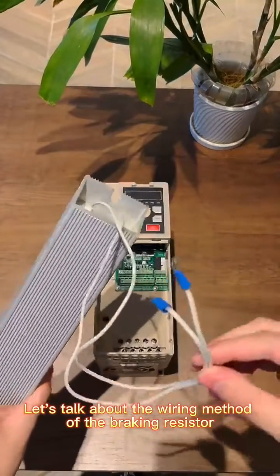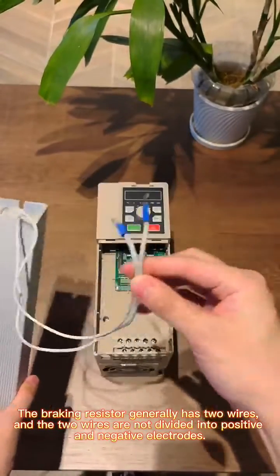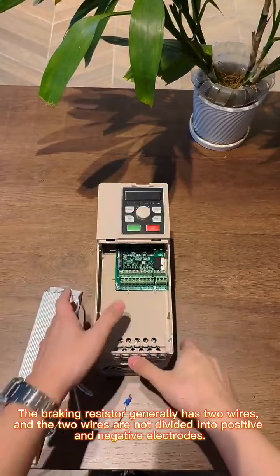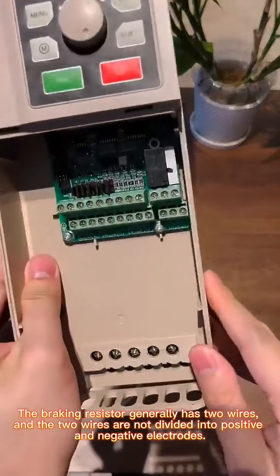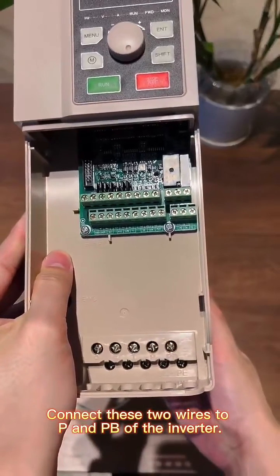Let's talk about the wiring method of the braking resistor. The braking resistor generally has two wires, and the two wires are not divided into positive and negative electrodes. Connect these two wires to P and Pb of the inverter.